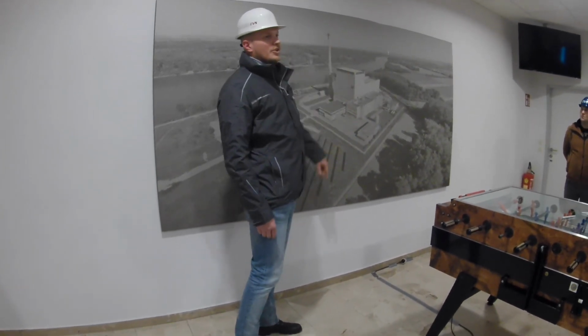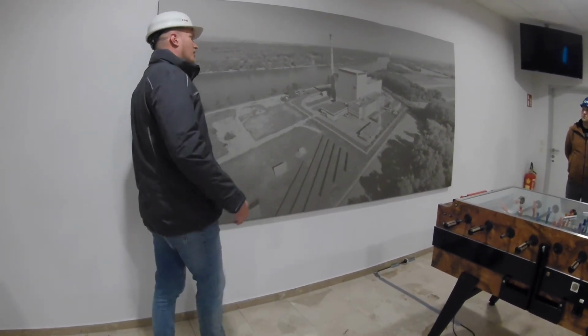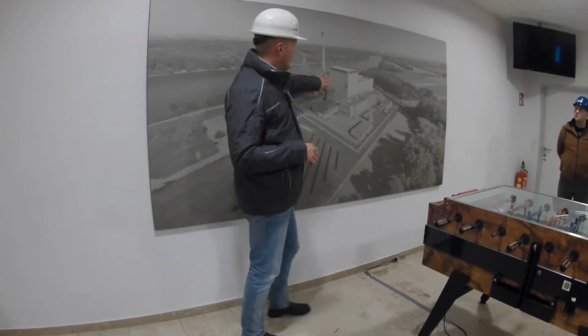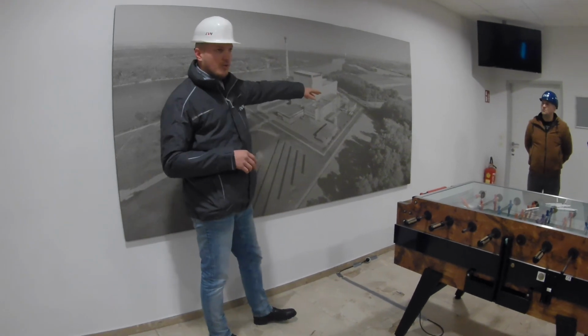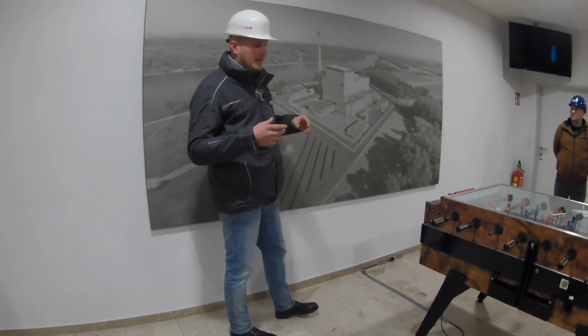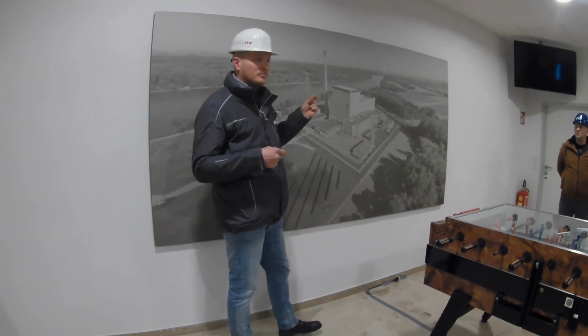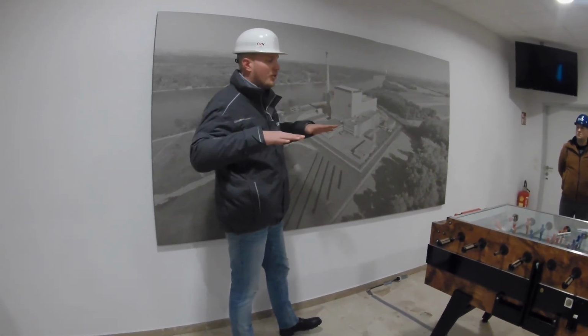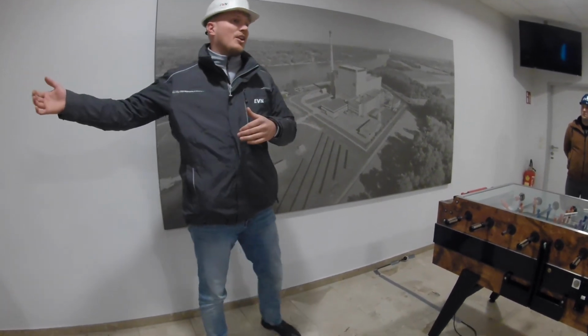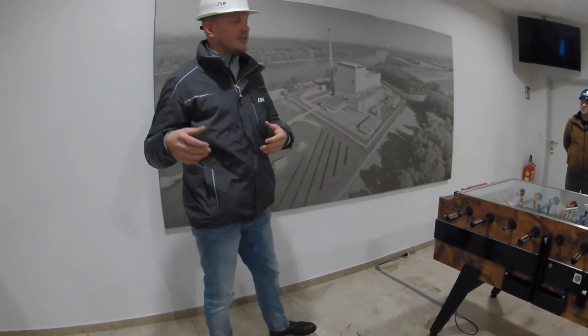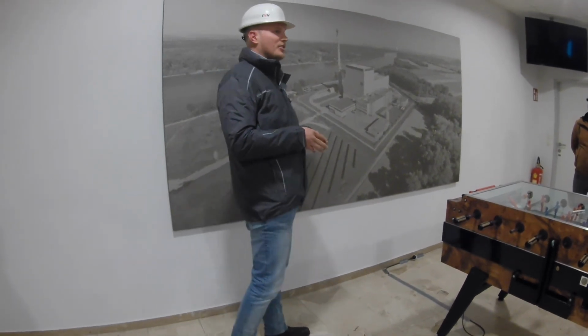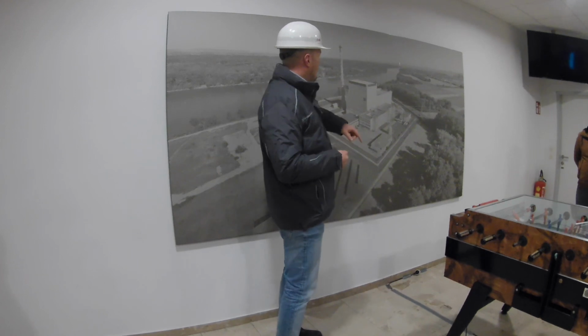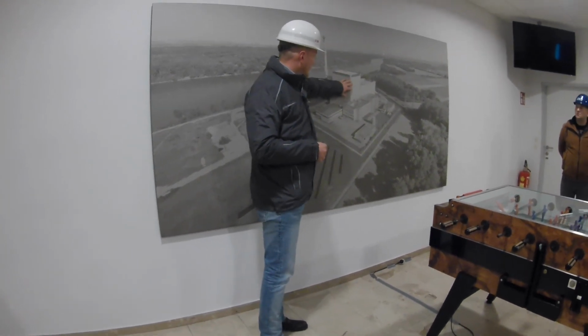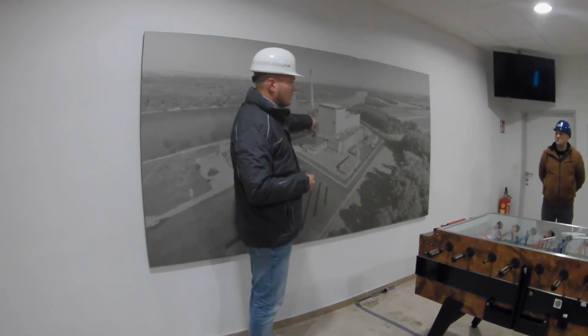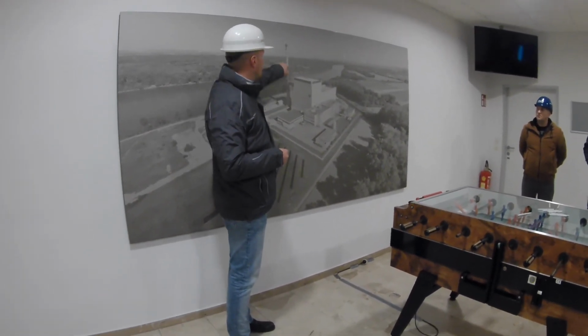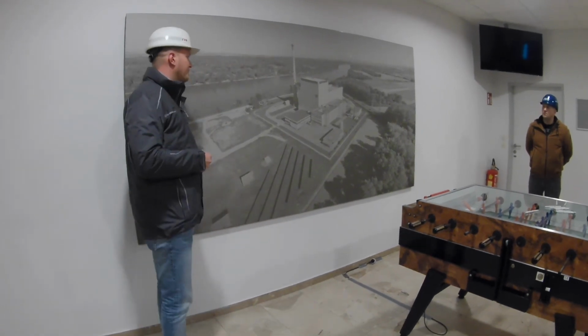Then we have the chimney, the final part of our huge air conditioning system, because the whole area, called the control area, where nuclear particles might possibly be in the air, is kept at a lower pressure, so that if you open a door, air comes inside and nothing goes outside - so you don't bring any nuclear particles uncontrolled into the environment. The air from inside the building goes through filters, then some delay areas, and then up through the chimney at 110 meters.